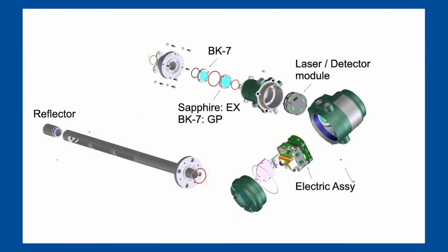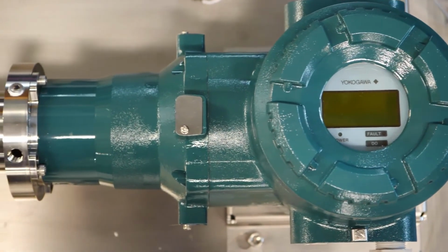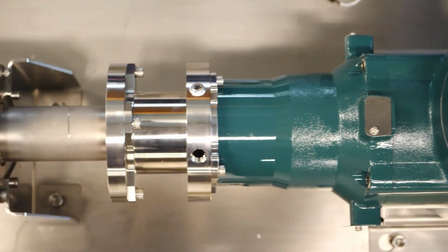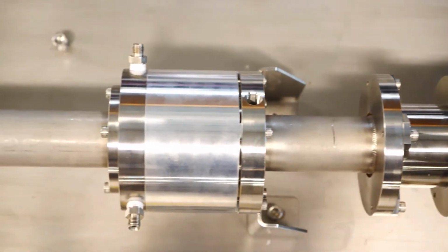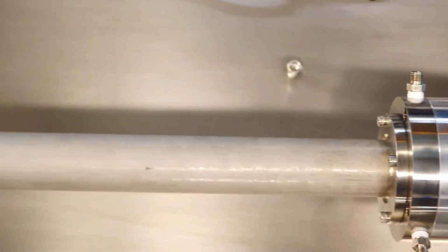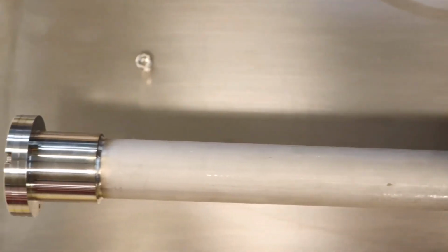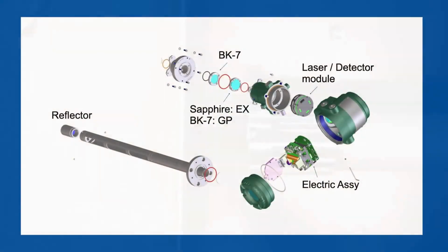The TDLS8100 has no moving parts and no consumables, meaning low long-term cost of ownership. It almost never requires calibration due to being built upon solid-state hardware and a direct absorption platform. Periodic validation can be performed instead at user-required intervals or to satisfy proof test interval requirements for SIS installations. The Smart Laser module stores all factory calibration data, so in the event of an accidental calibration, all settings can be restored to factory ones. This is significant because a replacement laser module, in the event that you flood the original one with dirty or wet purge gas, is plug and play, without the need to remove the analyzer for offline calibration. This keeps uptime maximized with our fully field repairable design.